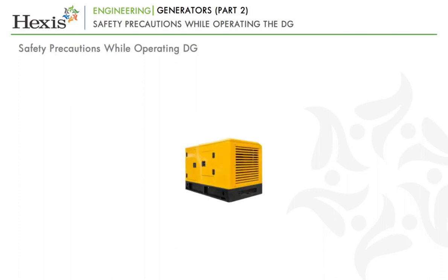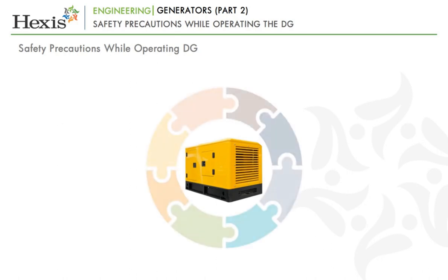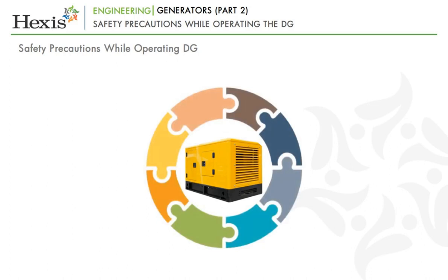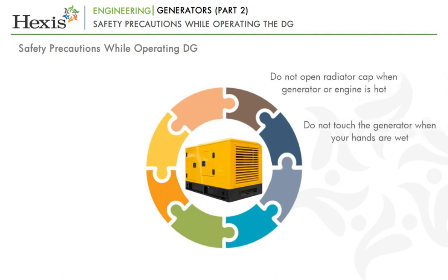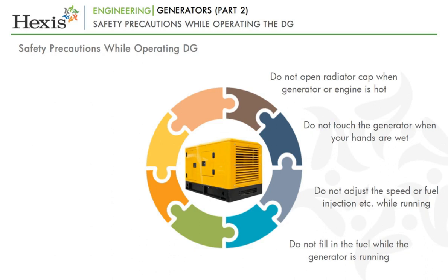As with working on all electrical equipment and devices, there are some basic safety precautions that must be taken during its operations, especially since DGs supply high voltage currents. Therefore, for any personnel who operates the DG, the following safety precautions need to be taken very seriously. Do not open a radiator cap when the generator or engine is hot. Do not touch the generator when your hands are wet. Do not adjust the speed or fuel injection etc. while running. Do not fill in the fuel while the generator is running.